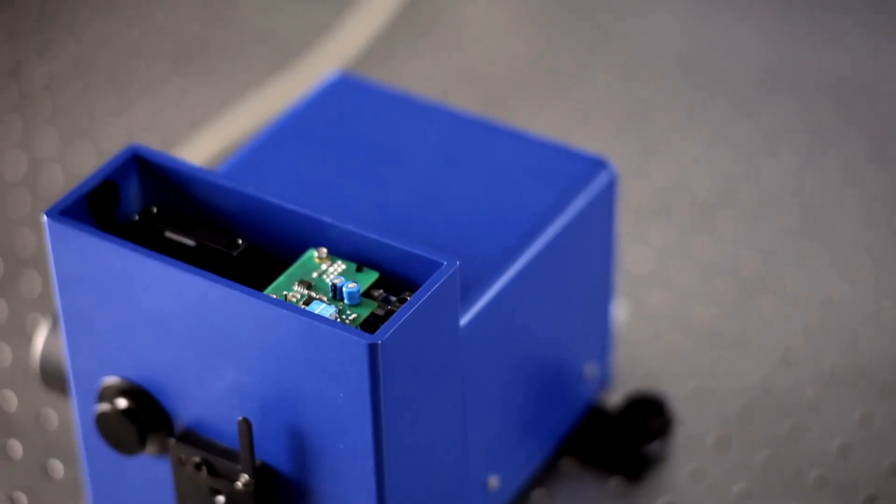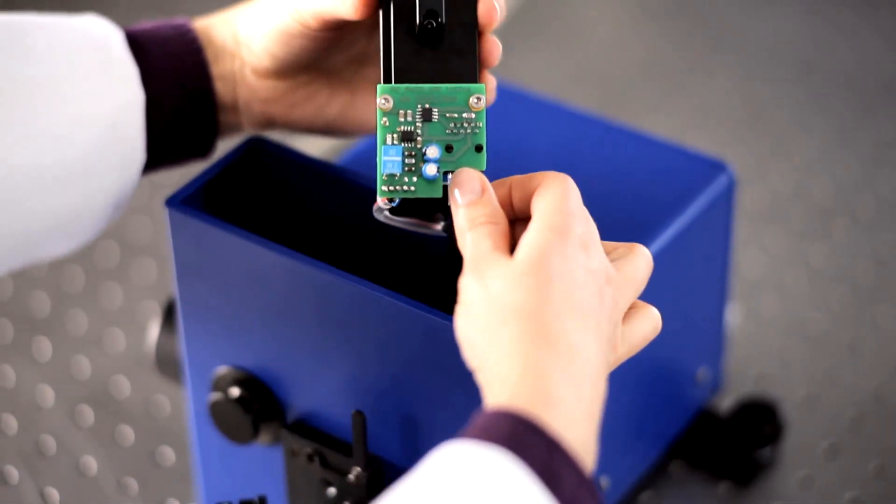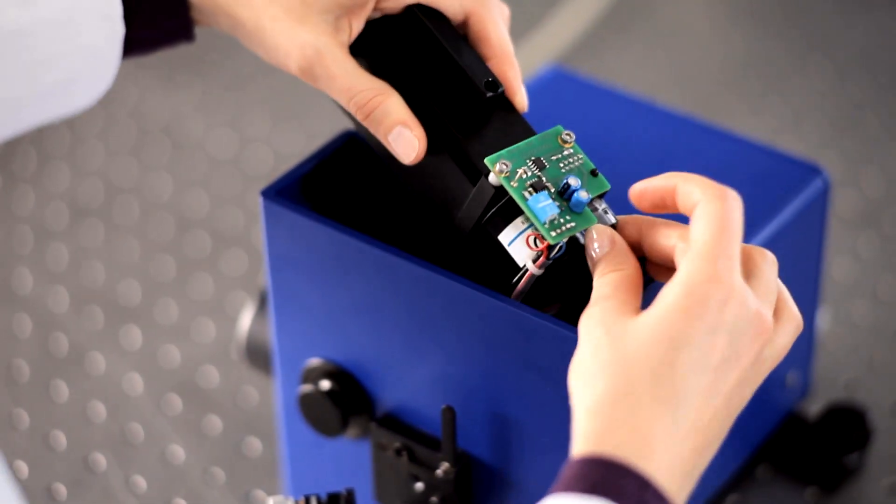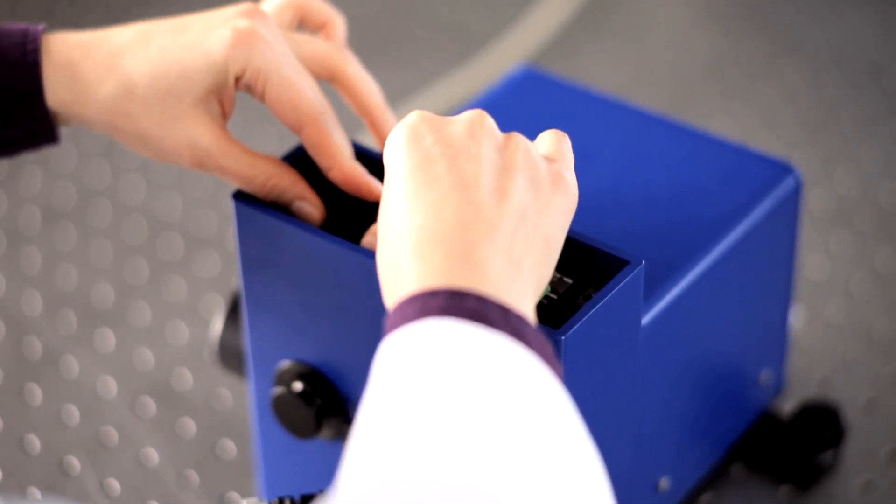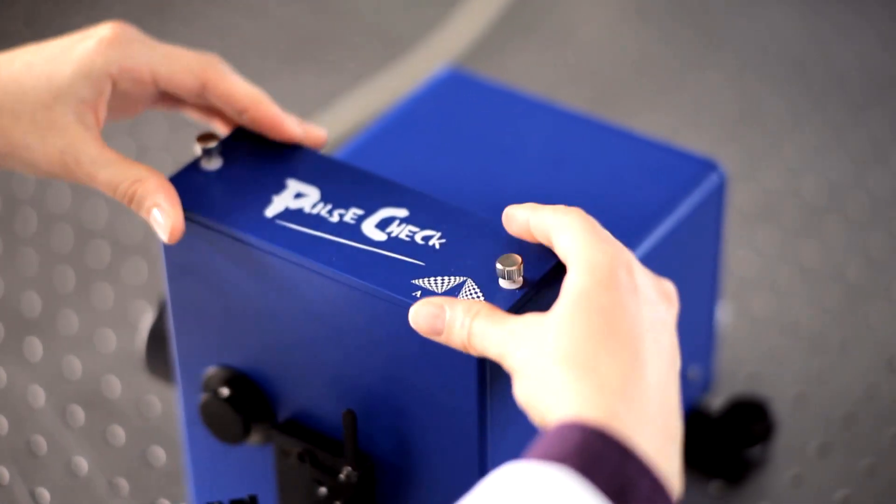Now, pull the retaining clip back and lift the detector unit out. Then unplug the connector. To replace the unit, plug in the connector, lower the unit into place, and listen for the click of the retaining clip. Then secure the lid. Simple.